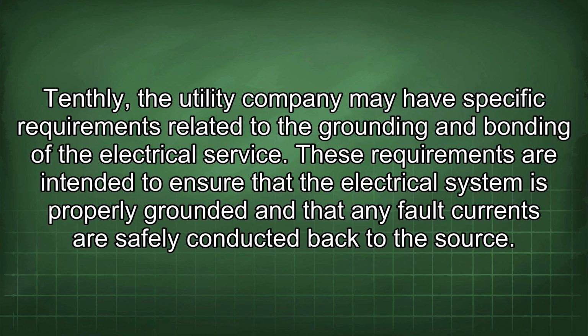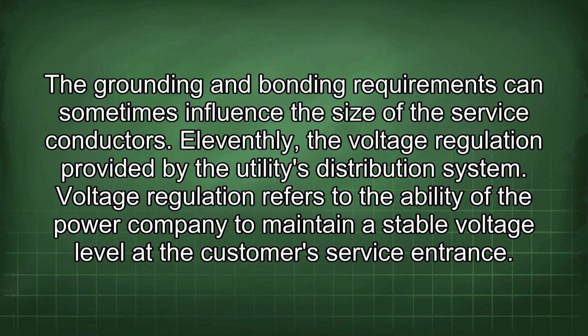Tenthly, the utility company may have specific requirements related to the grounding and bonding of the electrical service. These requirements are intended to ensure that the electrical system is properly grounded and that any fault currents are safely conducted back to the source. The grounding and bonding requirements can sometimes influence the size of the service conductors.